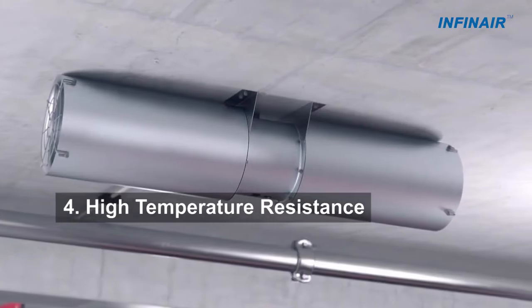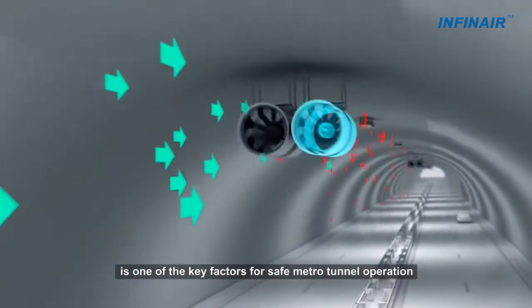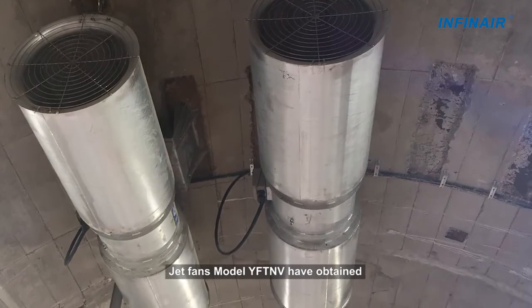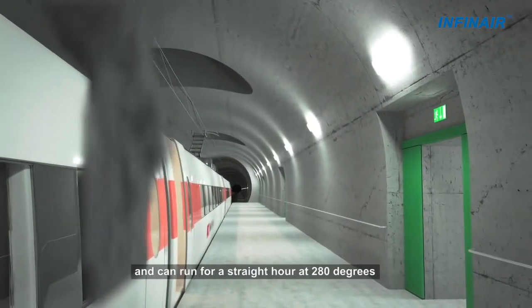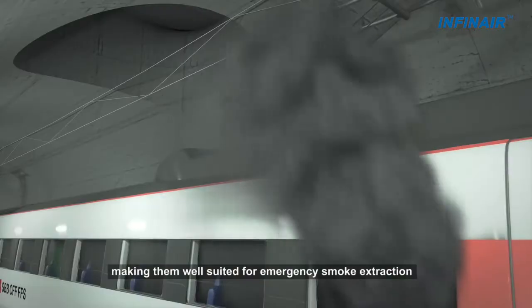4. High Temperature Resistance: The high temperature resistance level is one of the key factors for safe metro tunnel operation. Jet fans Model YFTNV has obtained CCCF certification and can run for a full hour at 280 degrees Celsius, making it well suited for emergency smoke extraction.